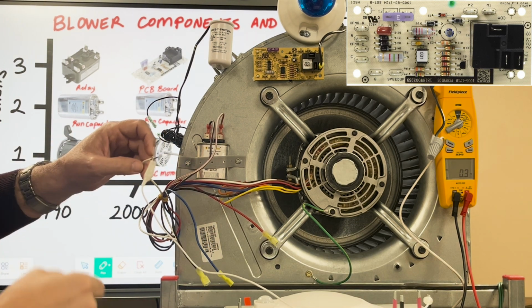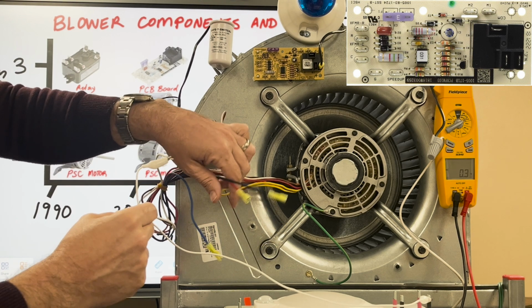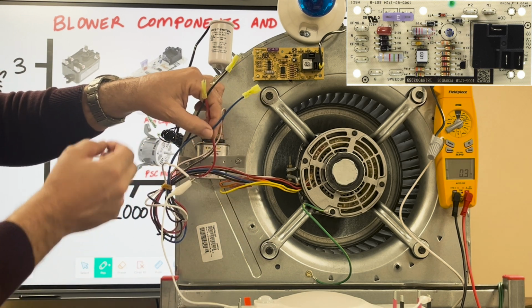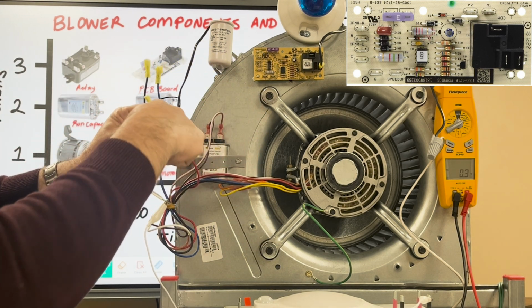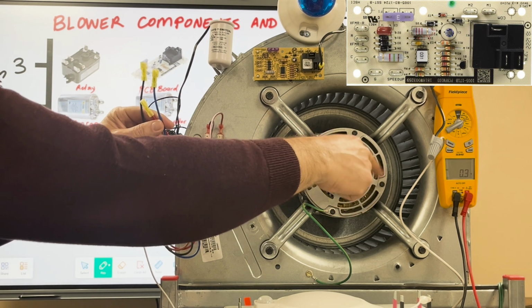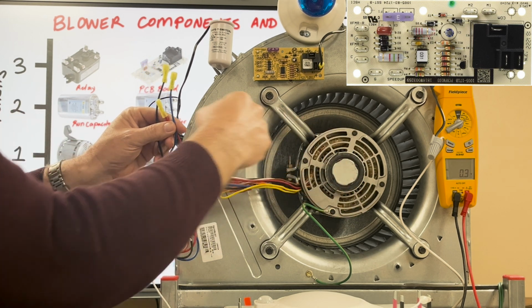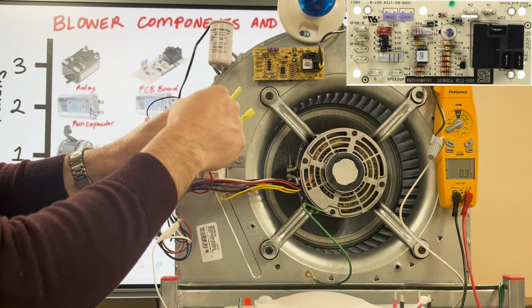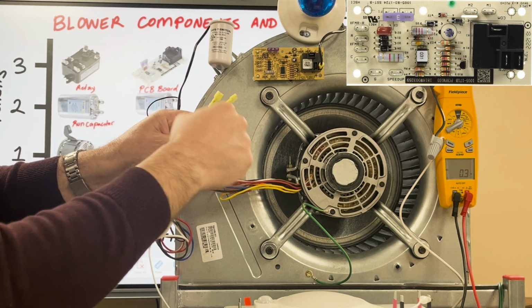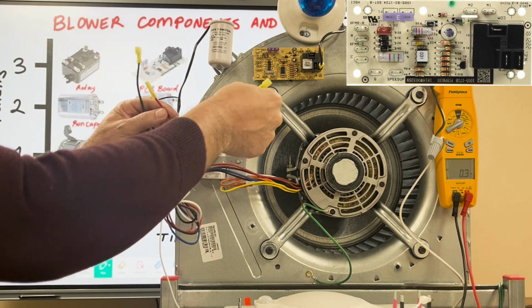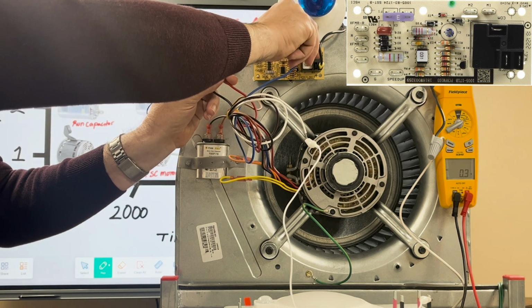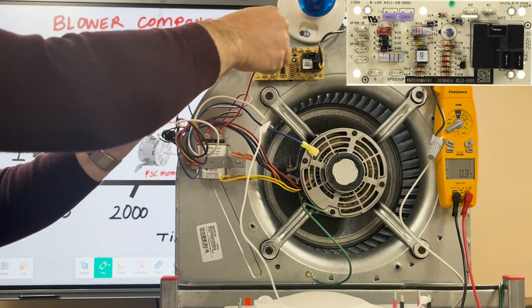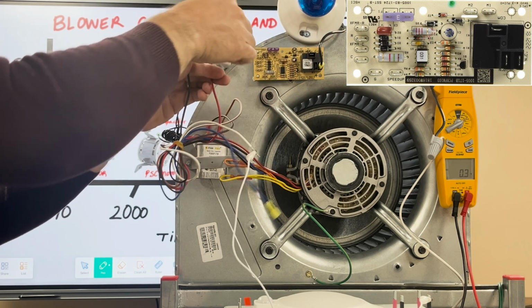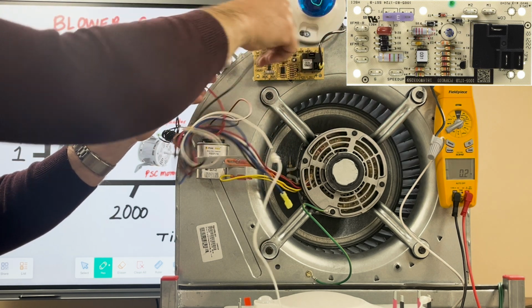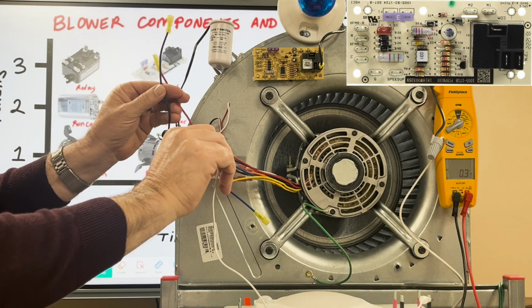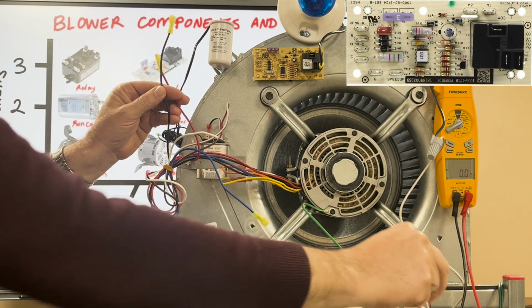And now we have 120 volts sitting on this wire. That 120 volts is running across my windings on my motor, putting it out on medium - black, high speed - and red, low speed. To show you there's power there, see how my light comes on every time I touch the terminal with a different speed. I'm going to go ahead and disconnect power here for safety.